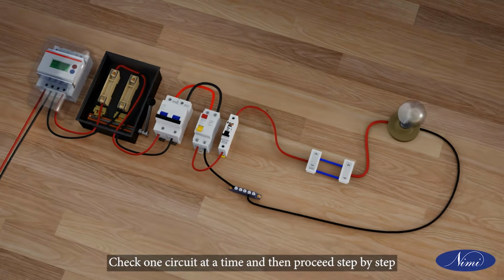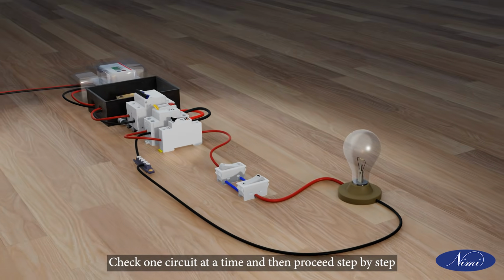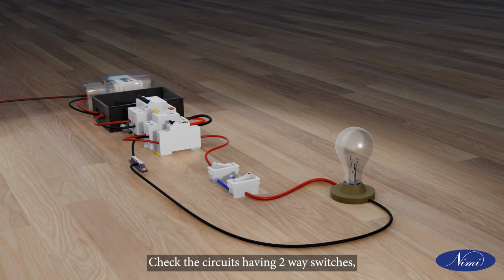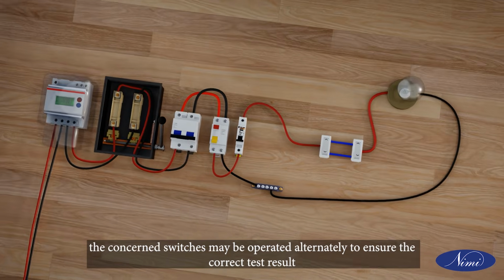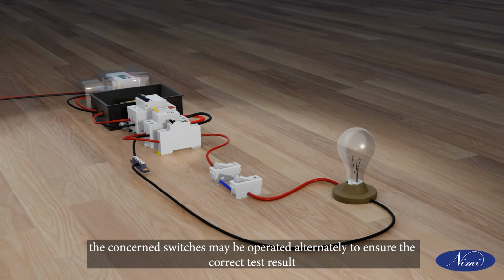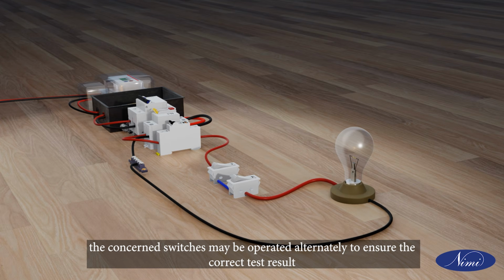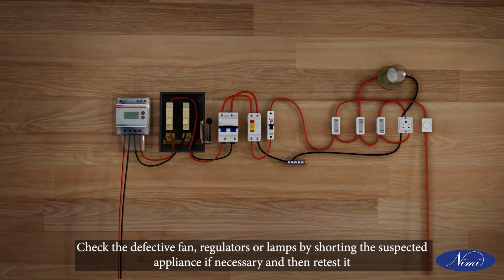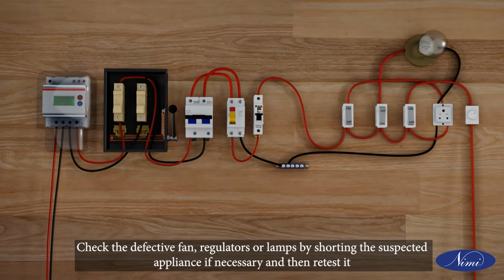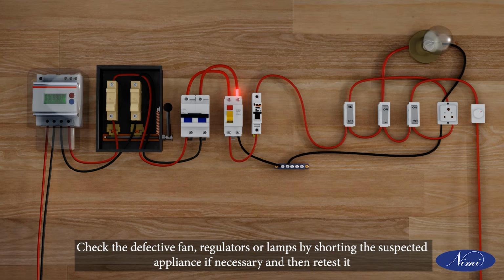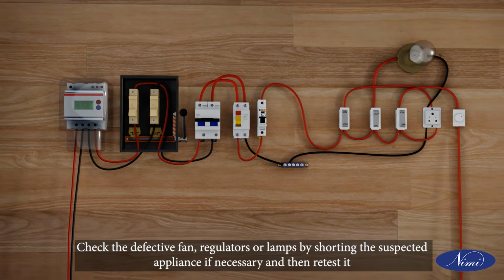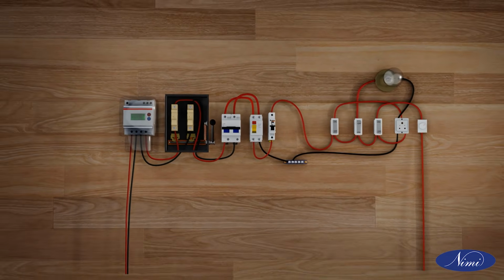Check one circuit at a time and then proceed step by step. Check the circuits having two-way switches. The concerned switches may be operated alternately to ensure the correct test result. Check the defective fan, regulators, or lamps by shorting the suspected appliance if necessary and then retest it.